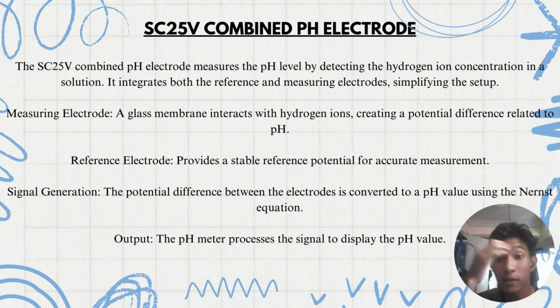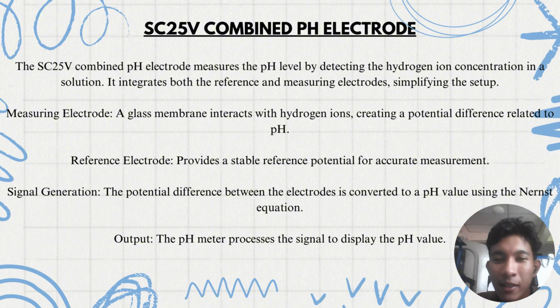Hi, my name is Muhammad Iqbal. I will present about the SC25V combined pH electrode. The SC25V combined pH electrode measures the pH level by detecting the hydrogen ion concentration in a solution. It integrates both the reference and measuring electrodes, simplifying the setup. Measuring electrode: its function is that a glass membrane interacts with hydrogen ions, creating a potential difference related to pH. The reference electrode provides a stable reference potential for accurate measurement.